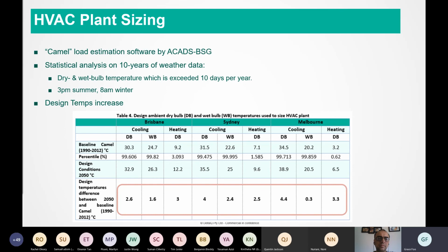The main takeaway from this is that in table 4, you can see that I've actually marked up the design temperature difference between using a 2050 file versus the baseline file in Camel, which is actually based off 1990 to 2012 data. Is about 2.6 degrees Celsius. Well, actually, on dry bulb, it ranges between 2.6 and 4.4, depending on location. And then on wet bulb temperature, it ranges between 0.3 degrees Celsius increase up to about 2.4 degrees Celsius. And then on the heating design temperature, it roughly sits around the 3 degrees mark increase.